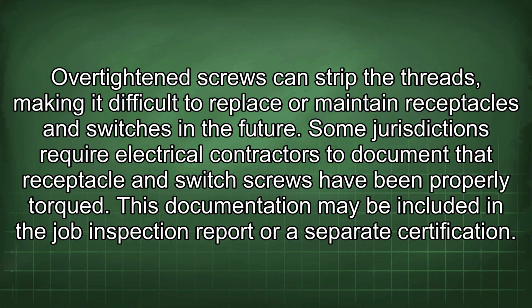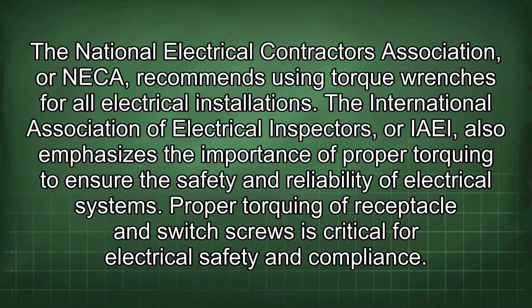Some jurisdictions require electrical contractors to document that receptacle and switch screws have been properly torqued. This documentation may be included in the job inspection report or a separate certification. The National Electrical Contractors Association, or NECA, recommends using torque wrenches for all electrical installations.